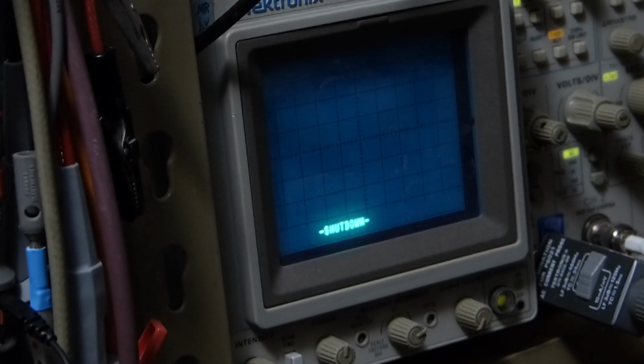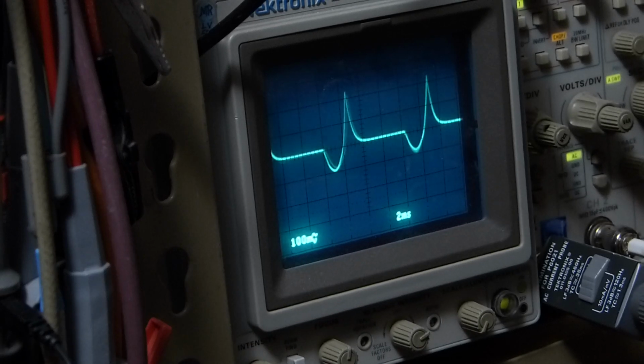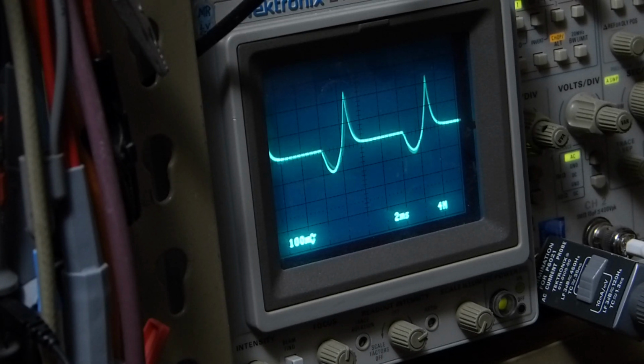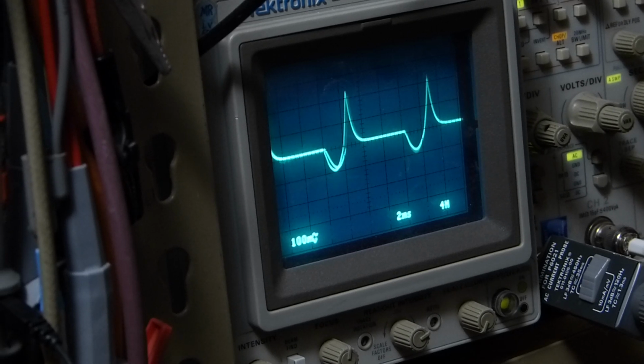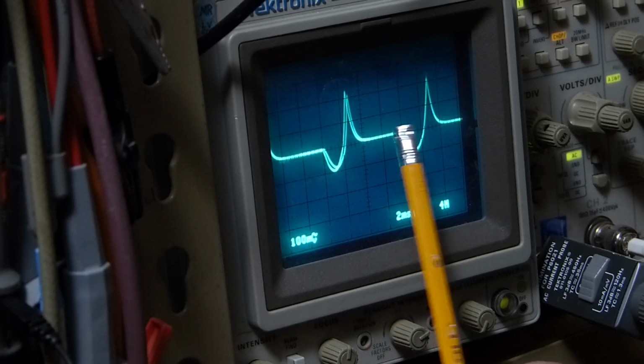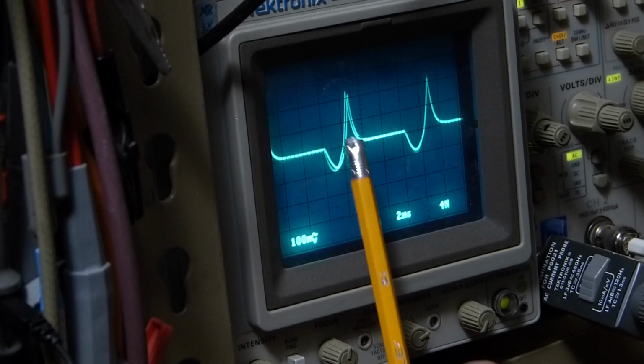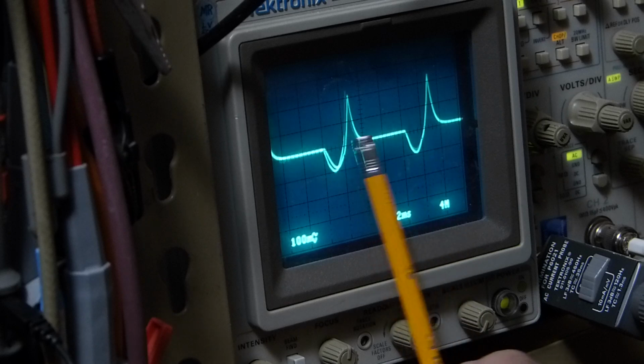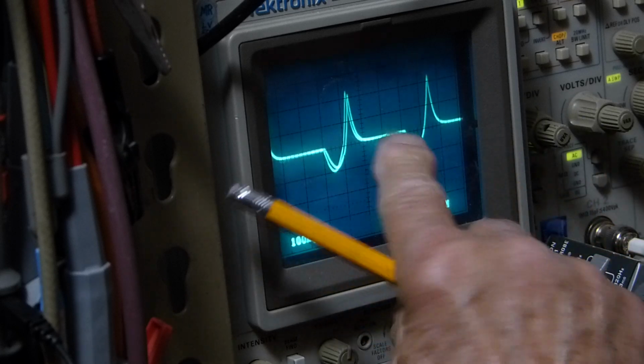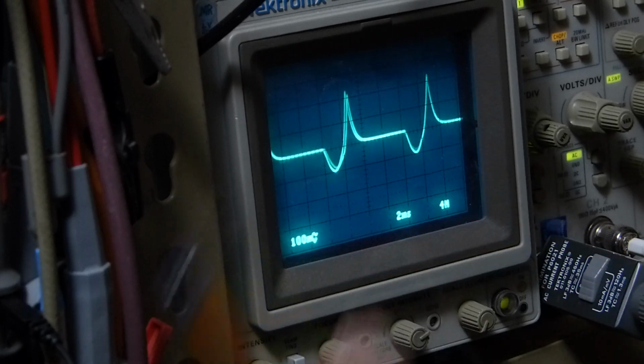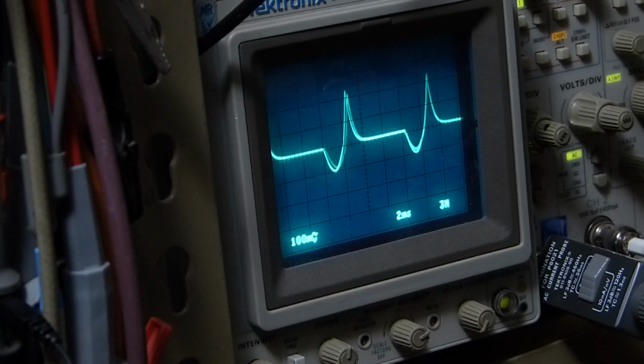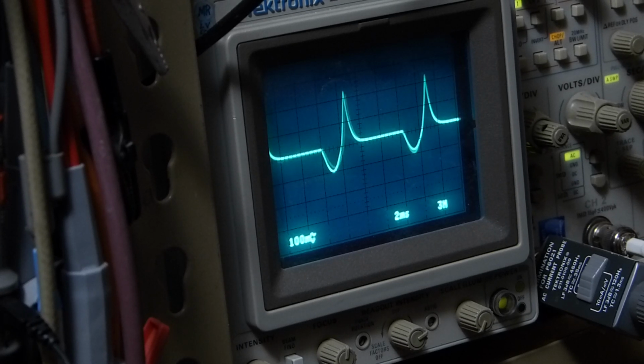Let's scope in here on the scope and get it to turn back on. See, that's the current that's flowing through that wire. Right here in the middle is zero. So we've got a positive pulse, then nothing flowing right there — no current — and then we get a negative pulse. Positive pulse, negative pulse. That's reality. Now, what we want for our relays and switches is this: relays and switches are rated differently for AC than they are for DC.